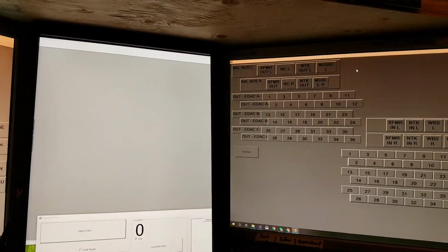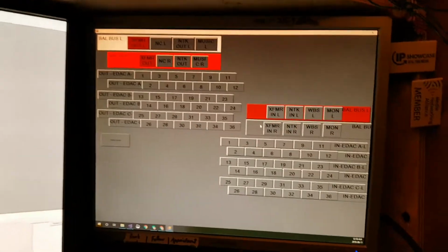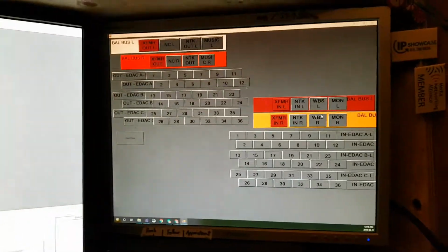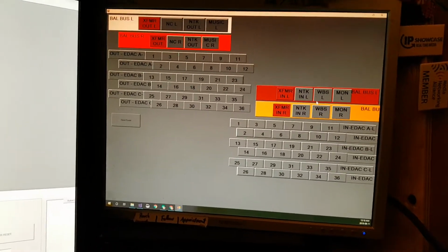So I have all these connections. Everything here is a connection. So I have a matrix router that allows me to make these connections. So if I want to make a connection from a balanced bus to a bunch of transformers, I do that. And what this is doing is sending relay contact closures. But it got really complicated to manage because I had all of these different devices.